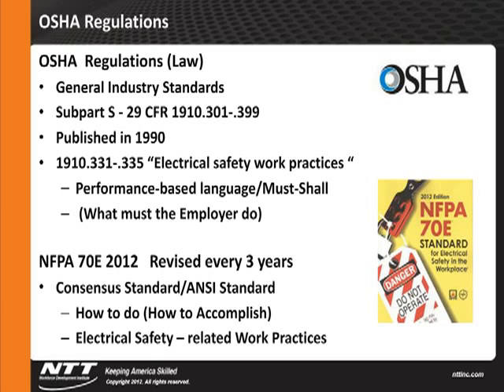Well, in the early 70s, OSHA went to the NFPA organization and asked them to write a set of consensus standards to help develop rules and practices at that time dealing with shock. Well, we've had quite a few revisions over the years, and in the year 2000, the industry recognized arc as a hazard also. And it's a consensus standard. A consensus standard basically is a best practice or how-to-accomplish standard. And as I go through this presentation, I'll read a thing or two to you that says if we follow the 70E, you'll be able to demonstrate to OSHA you're using industry-recognized practices.